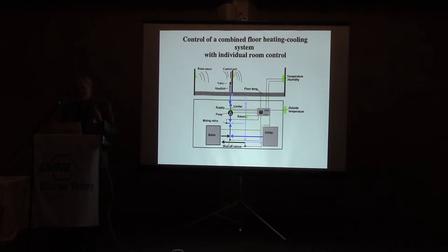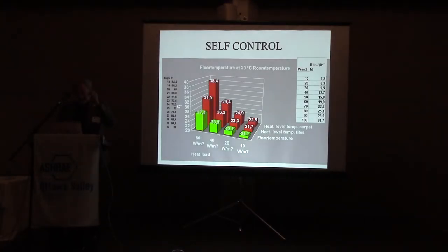But in most cases what we want is for the system to compensate for changes in internal loads from sunshine or from people. And here the systems are very efficient, because of the temperature difference. Here are some values from floor heating. The temperature difference between the floor and the room is in most cases, in a well-designed building, only a couple of degrees. So just a 1 degree change, for example a higher room temperature, will decrease the heat output to 30%. So there's a significant level of what we call self-control, and that means it is not really a slow system. We have several data on that. You have to distinguish between compensating for changes in internal loads and wanting to change the temperature in the space.